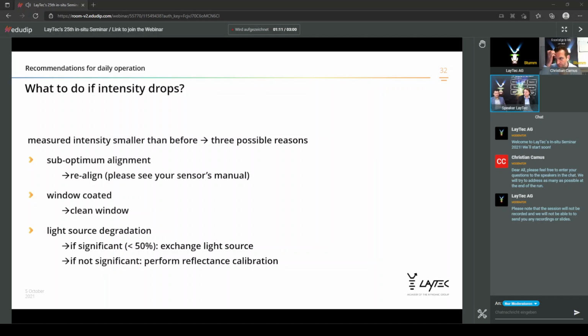And here, because of the problems we received from the field, you will receive new calibration data related to the new light source. This is important. And also if some of you are using replacement PCs, which you have in stock just in case, to get a quick reaction to get the system running again, we will support you to get the calibration data on the new computer. And then, hardware mixing sounds very bad. We will enable you to do that. What we would like to mention is you need to be careful. You cannot just do that.